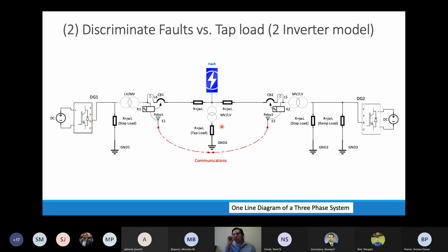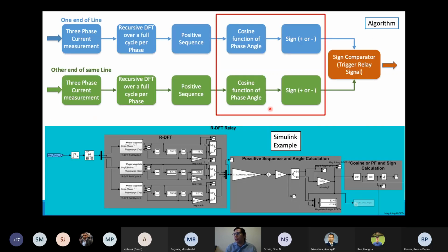And in the middle of the line, we will be testing a tap load and a fault. We know that any event can happen here, and not just in the middle. It can be on this end, or on this other end. And that's the reason we want to show how the relays communicate with each other in order to detect this type of fault or eventuality. So now I will talk about the cosine function of the angle and the sign, why we do this and why it's important in our method developed, after we verify our recursive DFT block diagram developed.